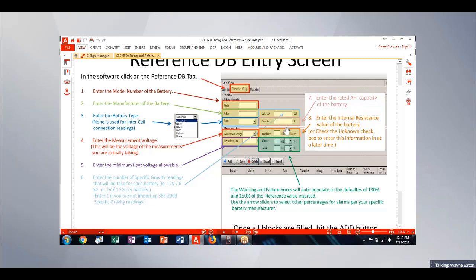And then finally, the impedance value or the reference value of what that battery's internal resistance should be when the battery is brand new. If I don't know that value, I can check the unknown checkbox, and it's going to put placeholders in there to store blanks so that I can come back in the future and put the correct value in there. Once I get all these entries into this table, I simply click add, and it adds that entry into my reference database.